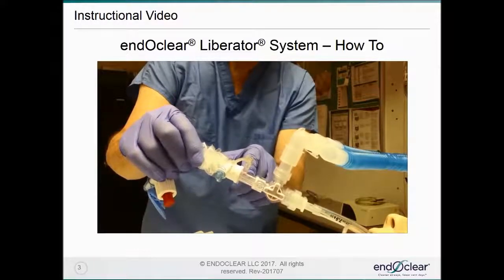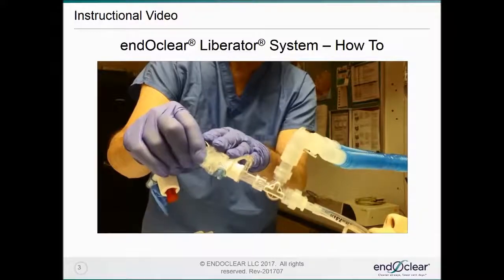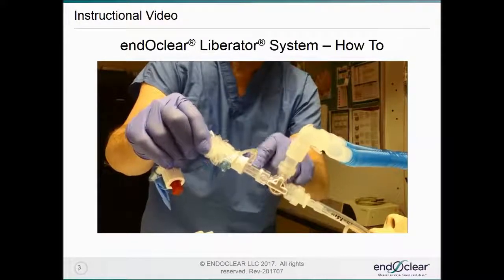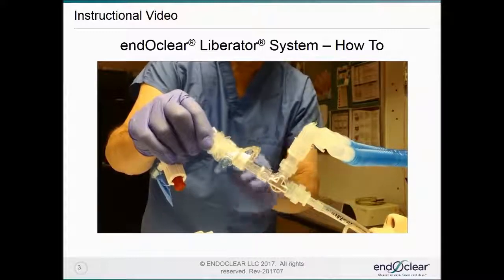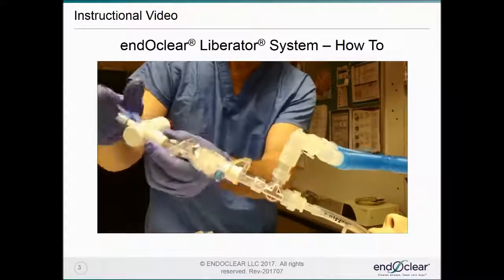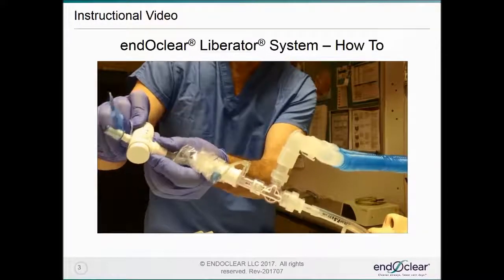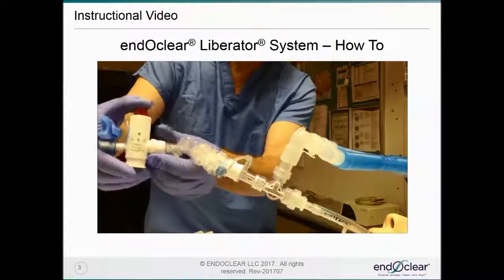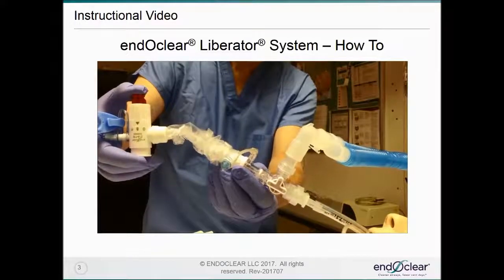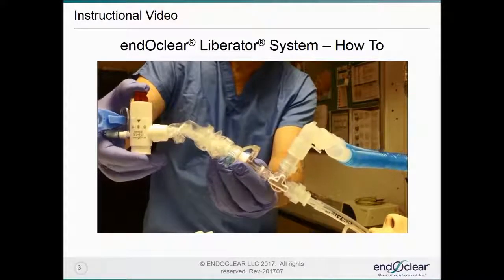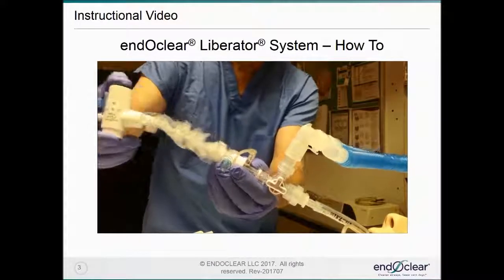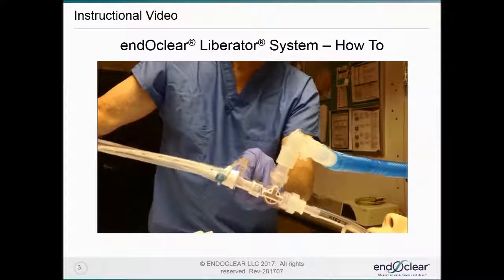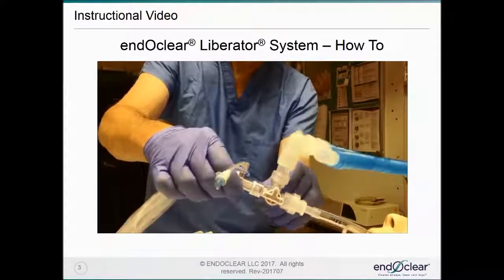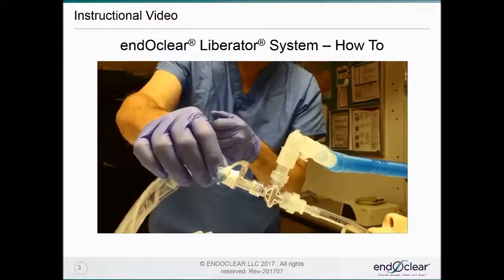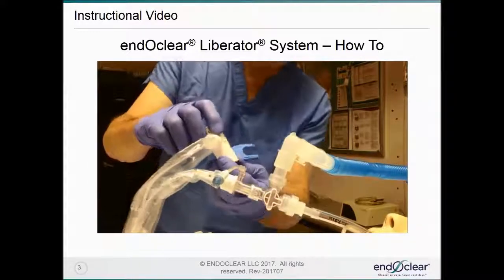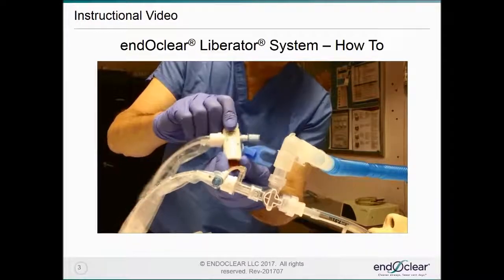What can subsequently be done is that every other time this device is used, the catheter can be inserted up to the 38 in this window and know that it's in the correct position distally. Once that's been done, the control is turned to wiper, and with a patient inspiration or a ventilator inspiration, the wiper is deployed and pulled back into the cleaning garage, and the stopcock is closed. At this point, the cleaning procedure is done by moving the control to suction.